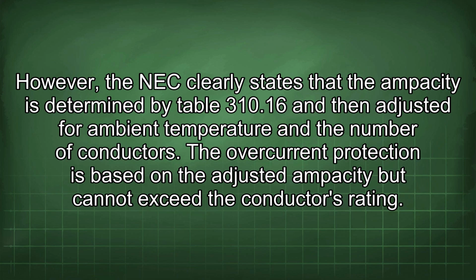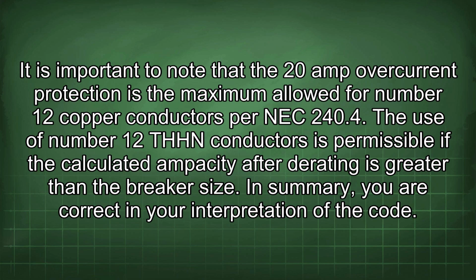However, the NEC clearly states that the ampacity is determined by Table 310.16 and then adjusted for ambient temperature and the number of conductors. The overcurrent protection is based on the adjusted ampacity but cannot exceed the conductor's rating. It is important to note that the 20 amp overcurrent protection is the maximum allowed for number 12 copper conductors per NEC 240.4. The use of number 12 THHN conductors is permissible if the calculated ampacity after derating is greater than the breaker size. In summary, you are correct in your interpretation of the code.